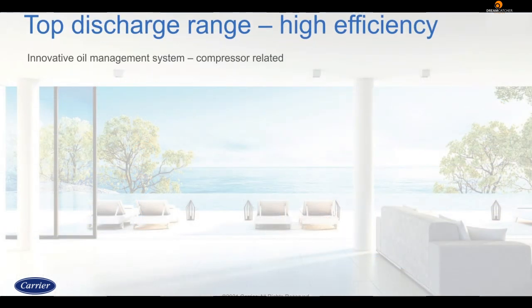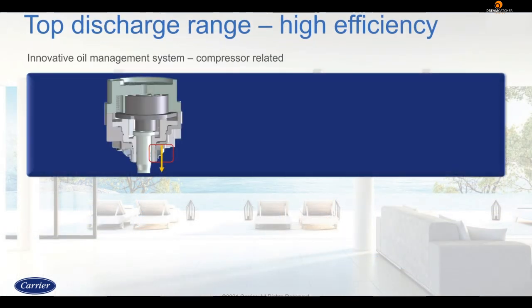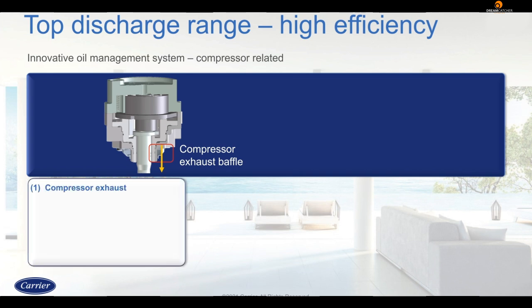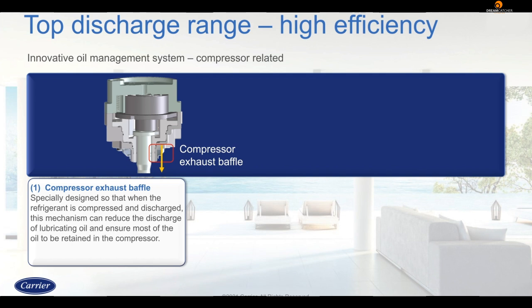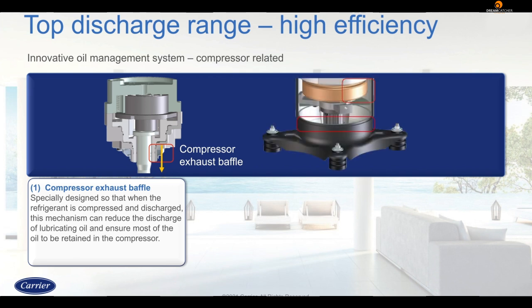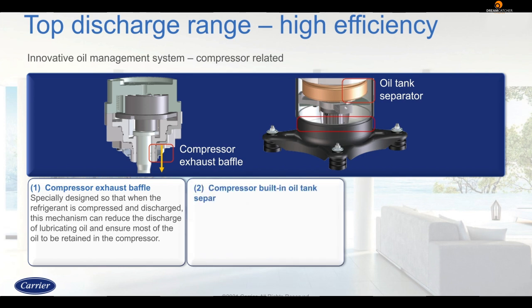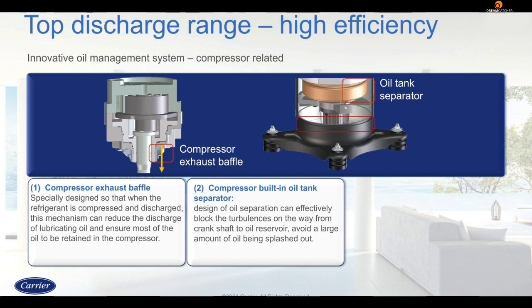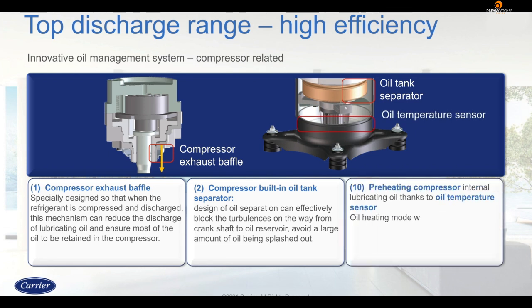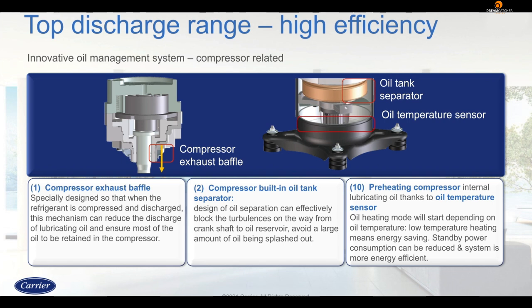The innovative oil management system is done through specially designed compressor exhaust baffle and ensures that when the refrigerant is compressed and discharged, the lubricating oil discharge is reduced, thereby ensuring that most of the oil is retained in the compressor. A specially designed built-in oil tank separator effectively blocks the turbulences when oil travels from the crankshaft to the oil reservoir, thus minimizing the oil from being splashed out. The oil temperature sensor preheats the internal lubricating oil, which in turn helps in energy saving.